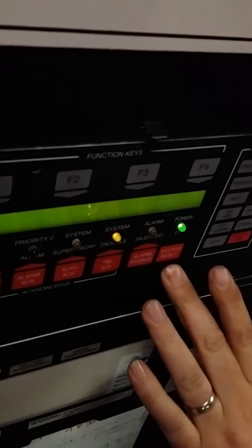You want to be careful hitting system reset. You can hit it right now. It's not a big deal. There you go, system reset. If you have a fire alarm and you do a system reset before the fire department says you're all set, all clear to clear your system, you will get a severe tongue lashing, and I will get a call the next morning saying, why did you press the system reset button before we checked it out?